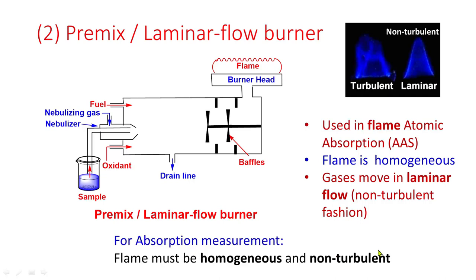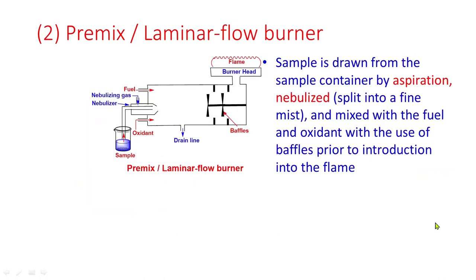For absorption measurement, the flame must be homogeneous and non-turbulent. The sample is drawn from the sample container by aspiration. It is then nebulized — that is, split into a fine mist — and mixed with fuel and oxidant using baffles prior to introduction into the flame.